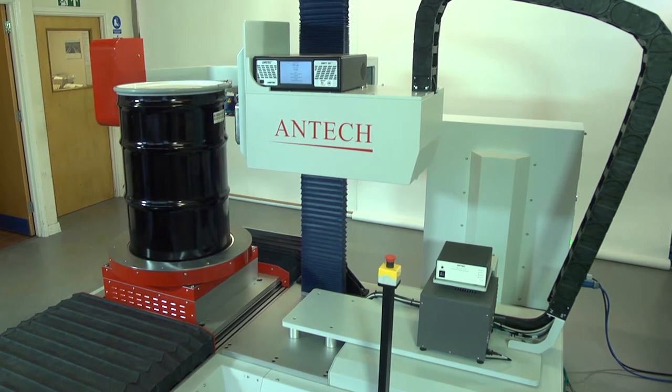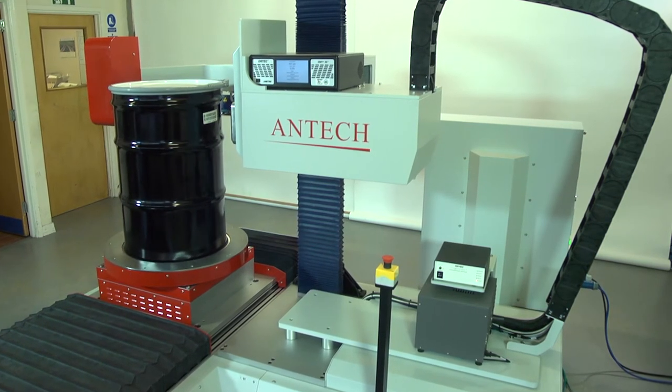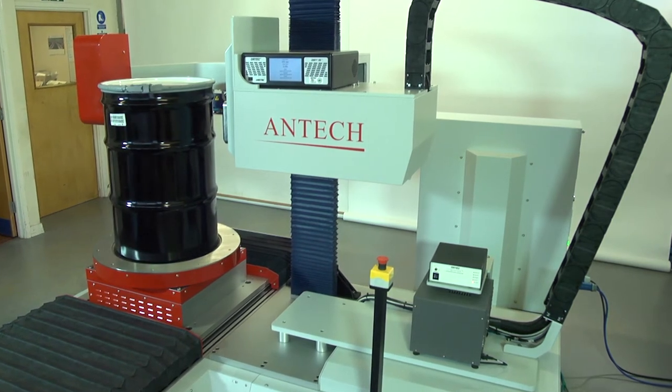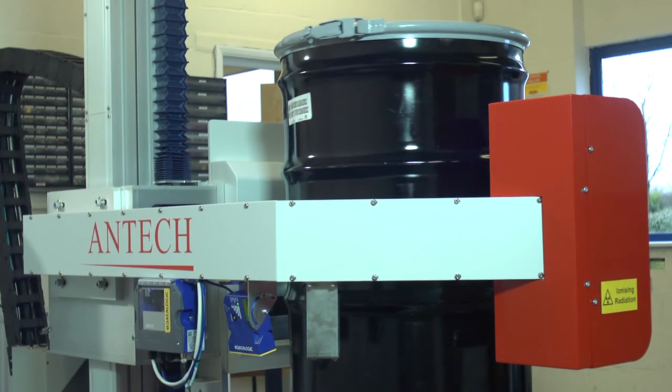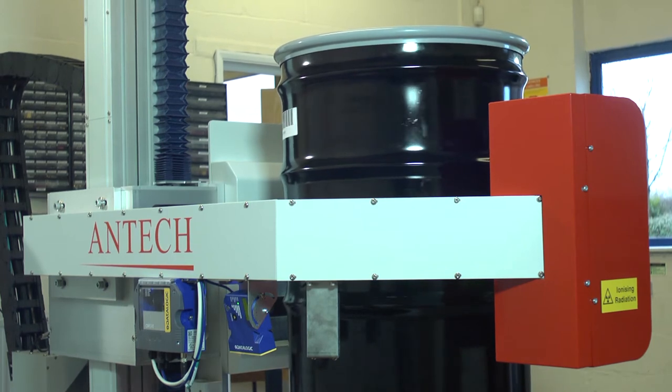The Antech Automated SGS Series 3200 incorporates enhancements to the measurement capabilities and operation of the original Los Alamos SGS, including a single lifting pillar for both the high-purity germanium detector and the transmission source shield and shutter mechanism, and a drum rotation platform mounted on slide rails.